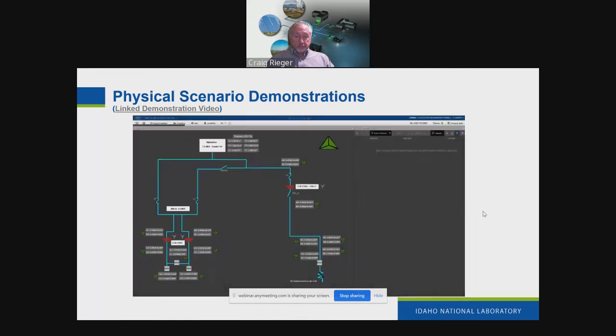The third test is a transient load change. This is meant to detect significant load changes, not small changes through routine operation of the system. In this case, we have a significant decrease in load at the station on the right. The state estimator generates an alarm and an alert message that can be reviewed if it's deemed necessary to do so.